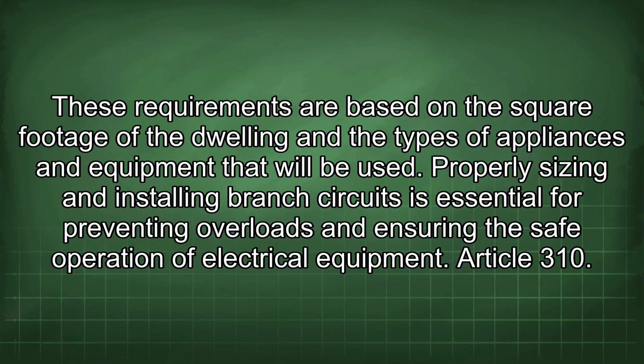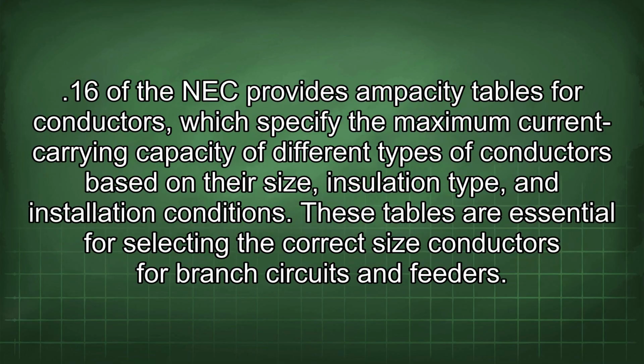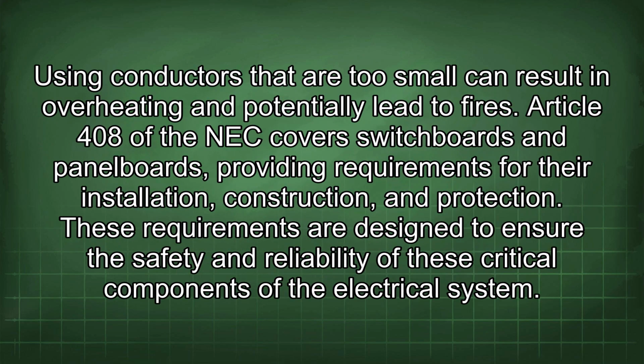Article 310.16 of the NEC provides ampacity tables for conductors, which specify the maximum current carrying capacity of different types of conductors based on their size, insulation type, and installation conditions. These tables are essential for selecting the correct size conductors for branch circuits and feeders. Using conductors that are too small can result in overheating and potentially lead to fires.